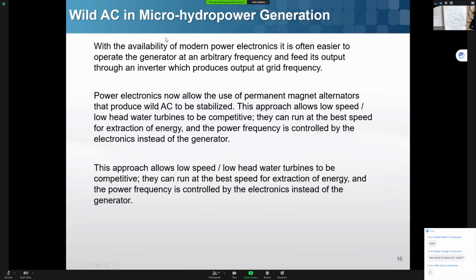So here they're talking about, for larger BC Hydro generators, you usually use a speed governor to control the rotating speed of those large generators. But here, we're just going to use some kind of power electronics like the rectifier and inverter. So it's easy to operate the generator when it has an arbitrary frequency, feed the output through an inverter. The inverter can control whatever required grid frequency and voltage.